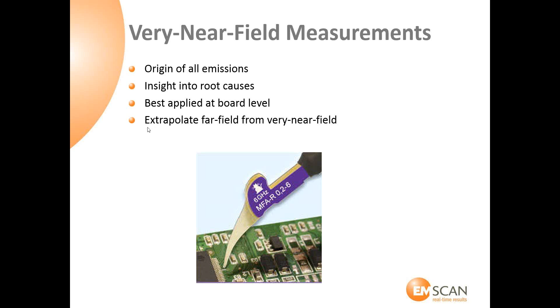Now we'll look at a very near field implementation, so something that can actually test in the very near field. And this is the basic technology. I mentioned before that we have an array of probes, and you can see here there are actually over 1,200 probes in this array, each one being a near field probe, very similar to what you might be familiar with as a handheld probe. The difference here is that you no longer scan that single probe. What we do is electronically switch to that array and capture all of the fields over the entire measurement surface in sub-second time.